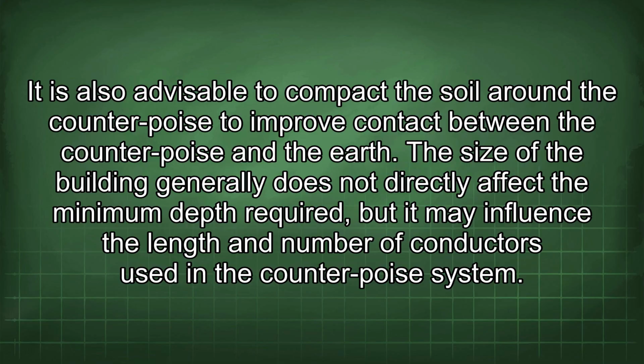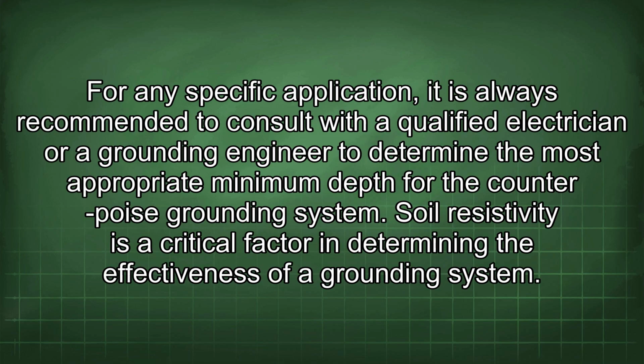The size of the building generally does not directly affect the minimum depth required, but it may influence the length and number of conductors used in the counterpoise system. For any specific application, it is always recommended to consult with a qualified electrician or a grounding engineer to determine the most appropriate minimum depth for the counterpoise grounding system.